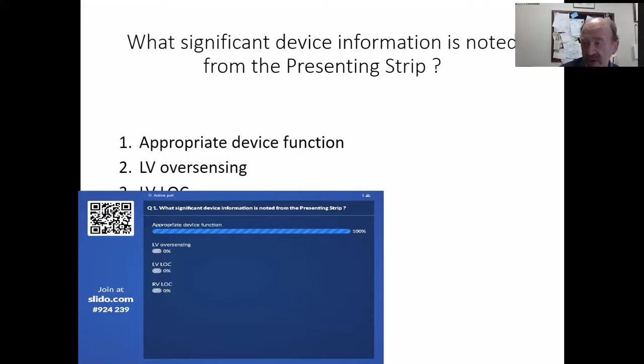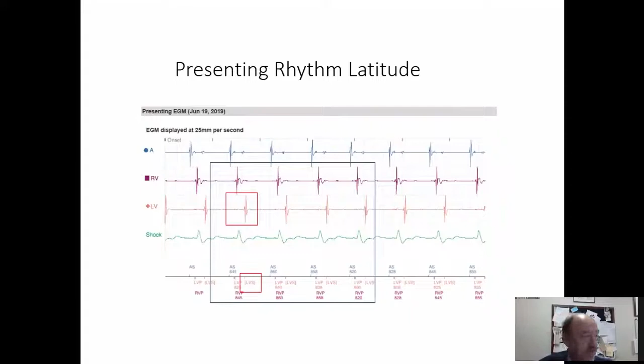So focus your attention on this part of the strip. It's just an example of what's going on, and you can see a pacing artifact here, and a pacing artifact here. You see the RV fairly close and the LV away. So you see LV pace and LV sense on the presenting rhythm strip. Although the device thinks it's pacing the LV 100% of the time, the problem is the device is not capturing the LV 100% of the time. That's how useful remote follow-up is in patients.